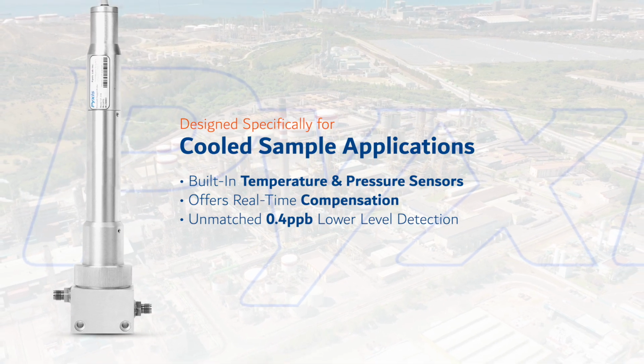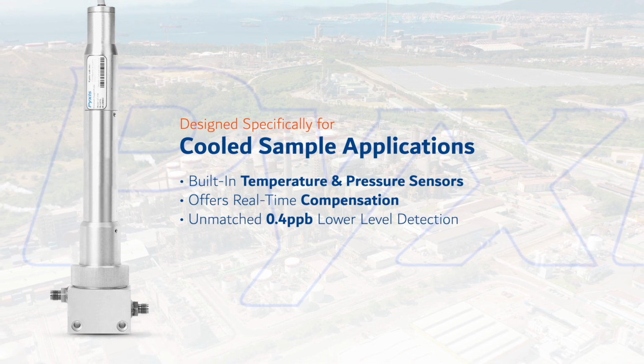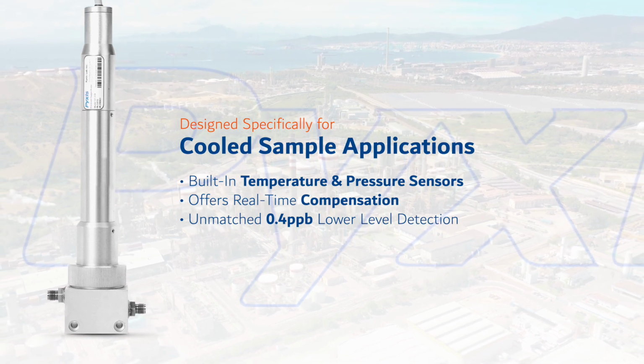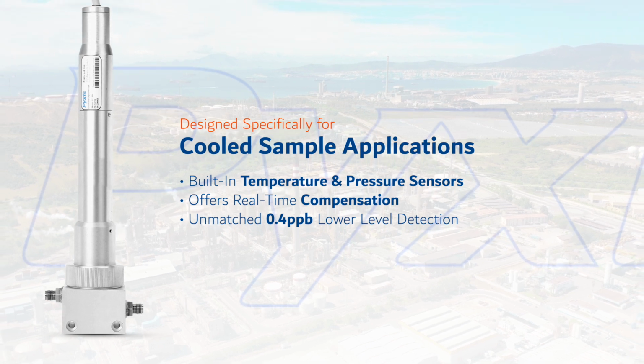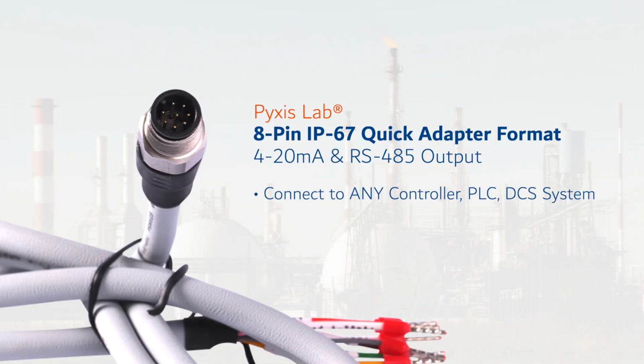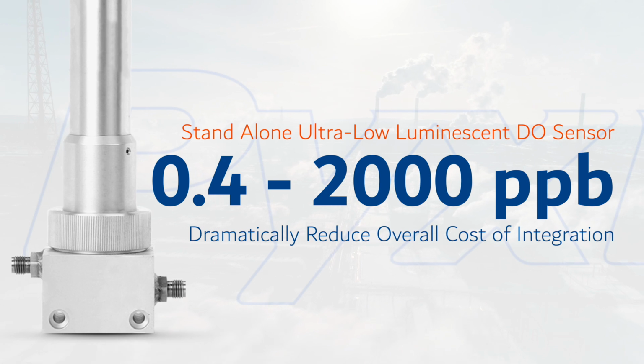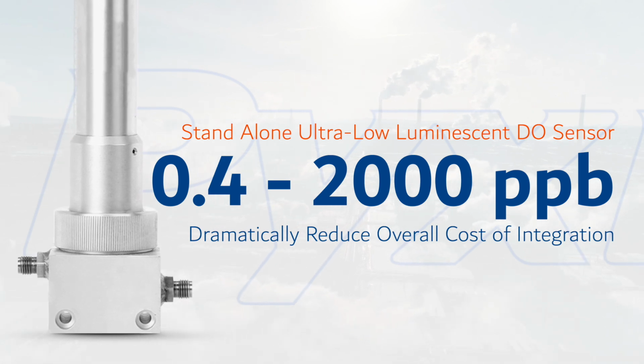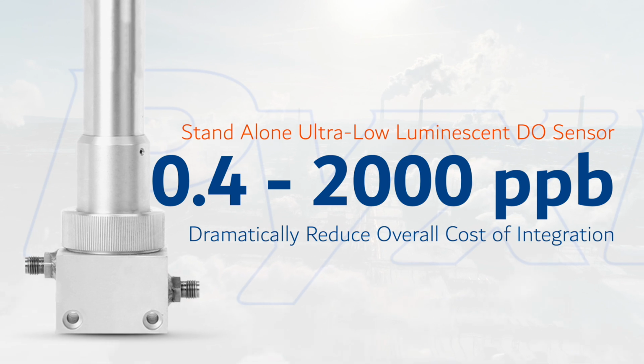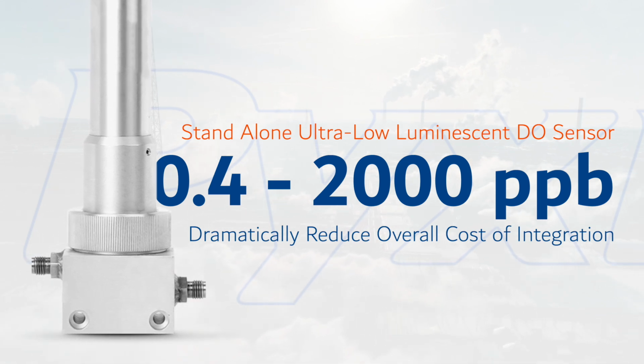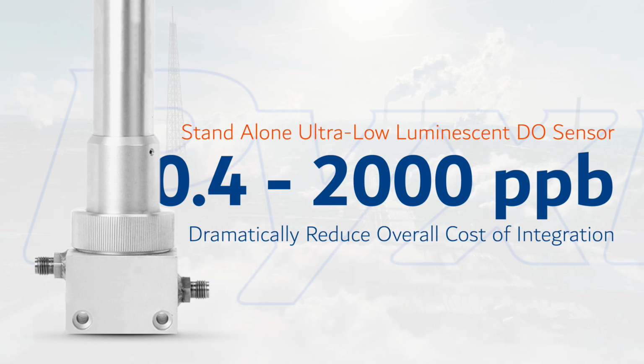The 0.4 ppb lower level of detection offered by the ST-774 is unmatched in the industry and is ideal for water and process applications requiring the utmost accuracy and range of detection. The ST-774 offers 4 to 20 mA and RS-485 output signals in an 8-pin IP67 quick adapter format, allowing direct connection to any existing controller, PLC, or DCS system without the need for any special controllers or transmitters. The sensor offers a detection range of 0.4 to 2000 ppb with real-time pressure and temperature compensation. Users may purchase the ST-774 as a truly standalone dissolved oxygen sensor and terminate it directly to their existing system at no additional hardware cost.